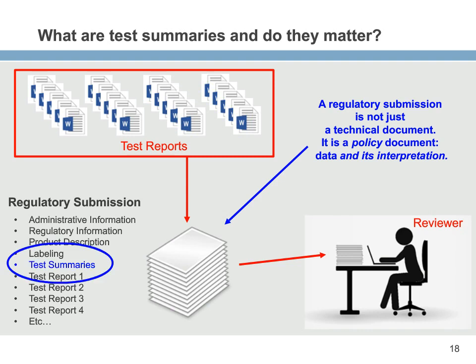So that's why, at least as we've written submissions, there's always, before you send in test reports, test summaries, something that helps the reviewer connect the test reports to the rest of the submission, but also connect those test reports to the accumulation of data that the reviewer sees in order to make a decision that this product is worth going to the market, it's ready, the risks have been minimized, the benefits are acceptable. Whatever the regulatory standard is, you are gently persuading the person that's reading this that, yes, this is acceptable going to the market. I've seen the disaster.